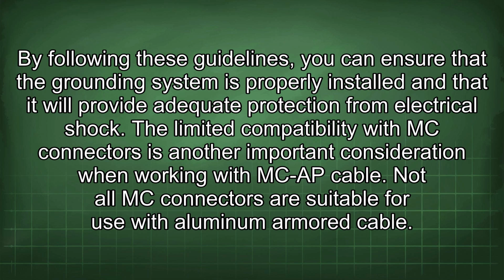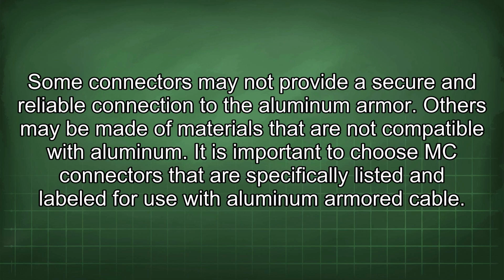The limited compatibility with MC connectors is another important consideration when working with MCAP cable. Not all MC connectors are suitable for use with aluminum armored cable. Some connectors may not provide a secure and reliable connection to the aluminum armor. Others may be made of materials that are not compatible with aluminum. It is important to choose MC connectors that are specifically listed and labeled for use with aluminum armored cable.